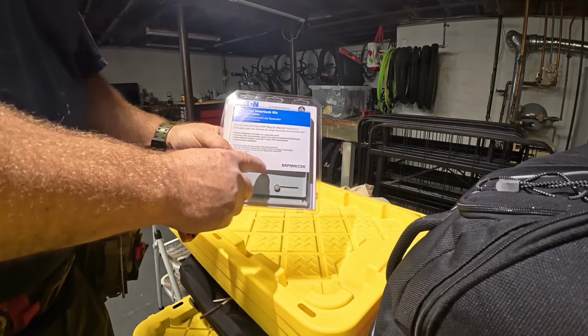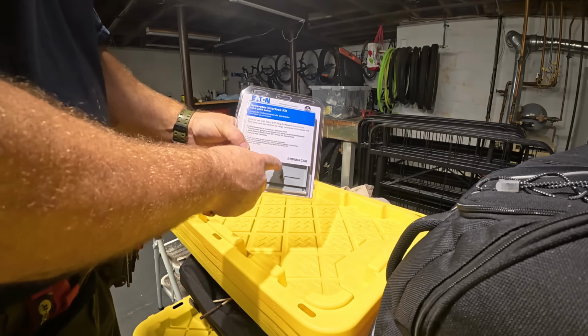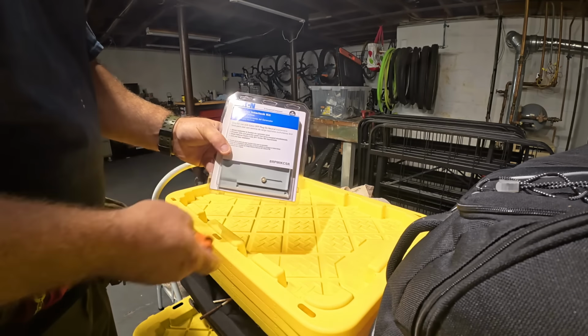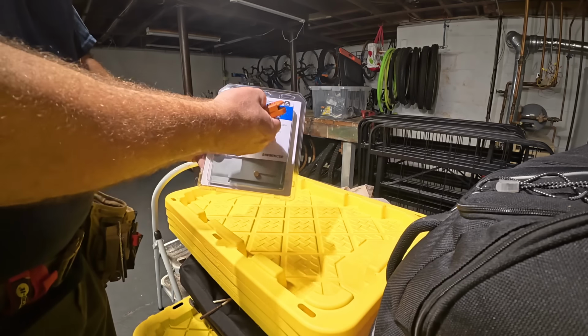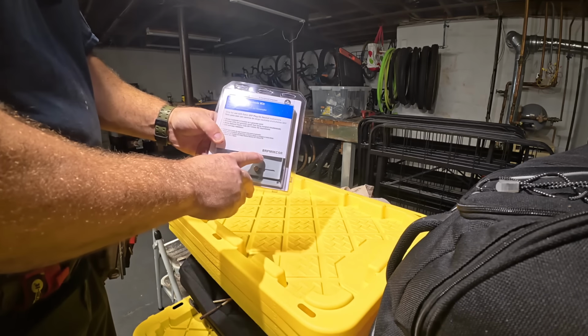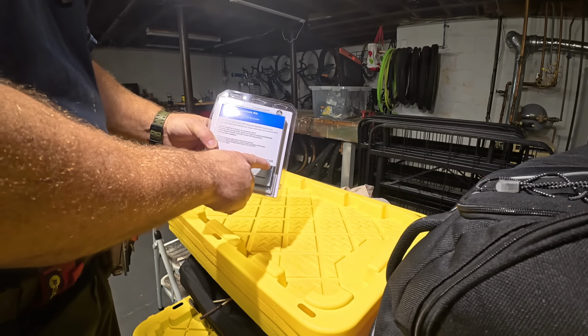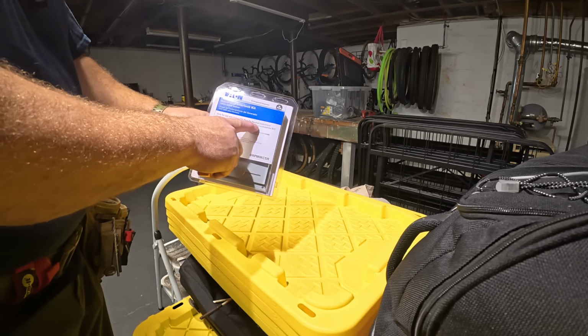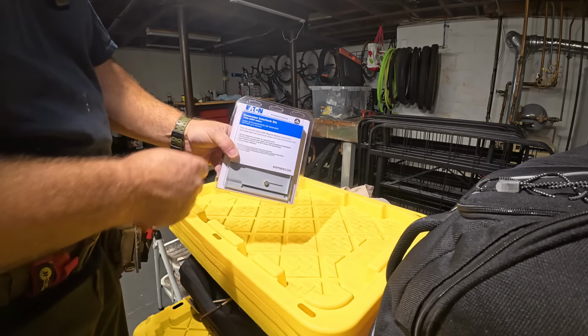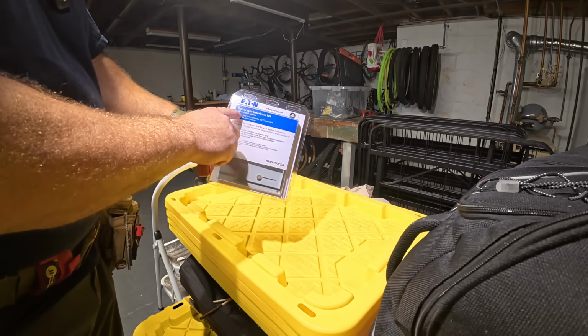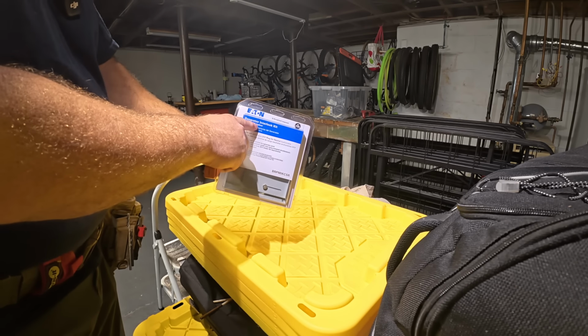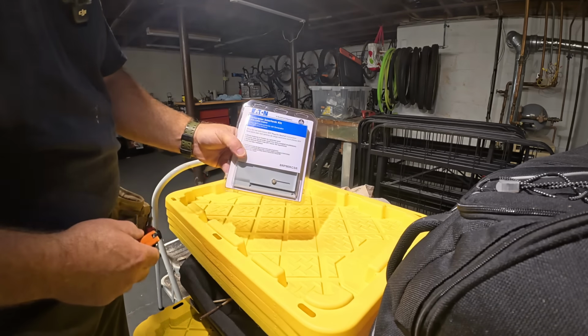Okay, so this is the listed interlock for this panel that we're going to put in. You can't just put in any other interlock that you want. It's got to be listed to be able to do this. This is the BRP MIK CSR. It's for the plug-on neutral load center, which is what we put in. It's good for a generator interlock kit for 150 amp to 225 amp indoor panel. So this is the one we're going to be using.